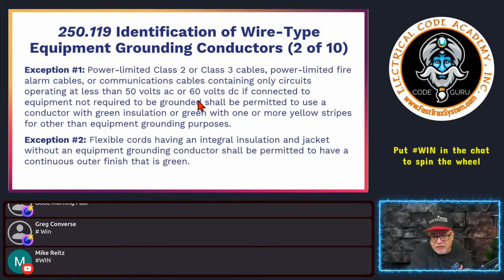So again, this may be in a pre-assembled cable assembly. Most of the time, the manufacturers who make the power limited Class 2, Class 3, or power limited fire alarm cables, if it works at those voltage classes, are not going to put a green in there. I mean, they're just not. That doesn't mean you couldn't have some imported product come in that might have something, but be careful of the voltage that you're working with in the system. So again, less than 50 volts AC or 60 volts DC, and it's connected to specific equipment that's not required to be grounded, okay? If that's the case, then the green or green with yellow may not be an equipment ground. So just be careful of that, all right?